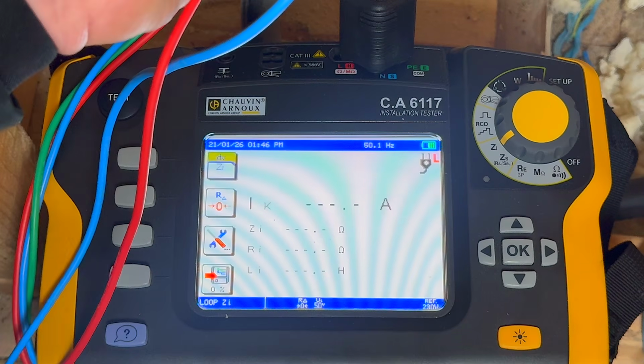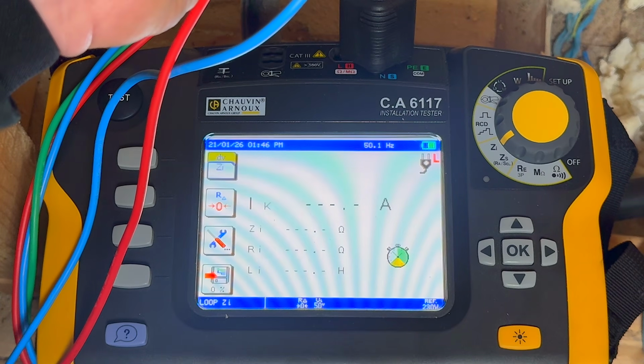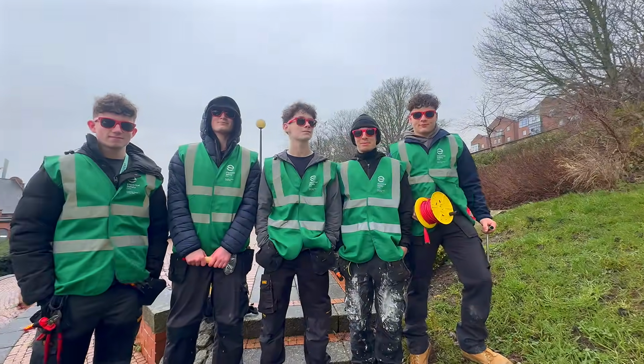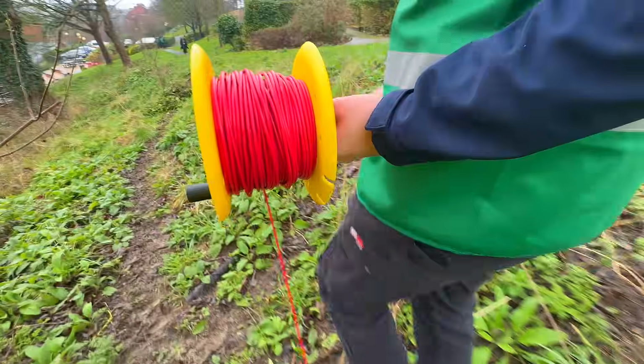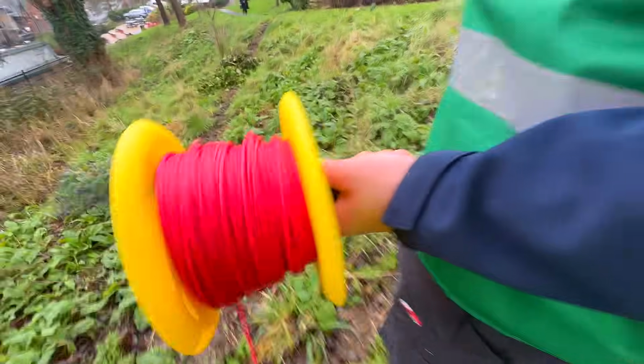A loop test can give you a number, and it is an important test to do to determine the disconnection time, but it does not isolate the earth electrode. But to show you how to test, I've dropped into Lincoln College with some very enthusiastic volunteers to take you through the process of the fall in potential method of earth electrode resistance testing.